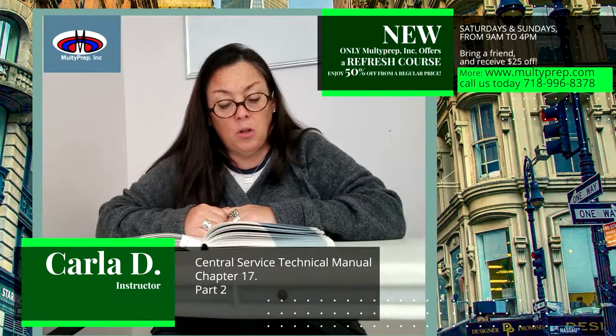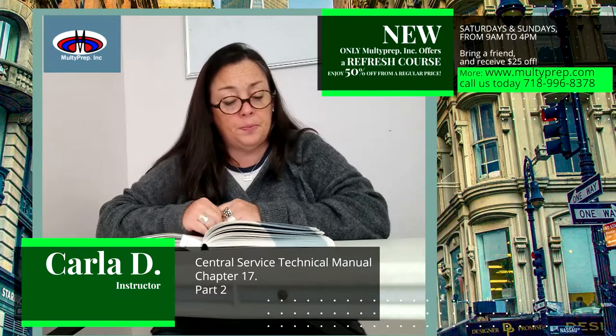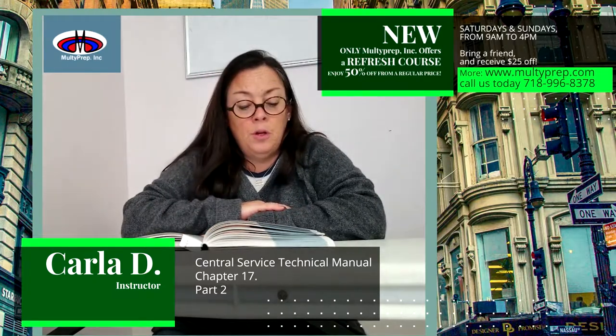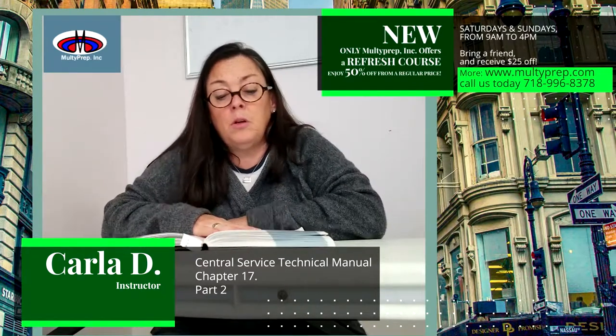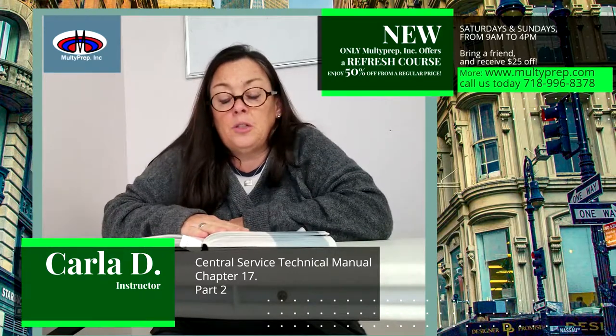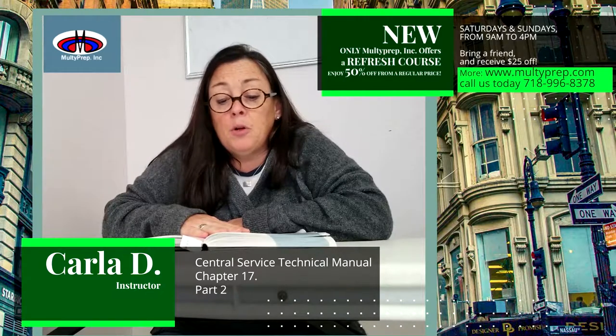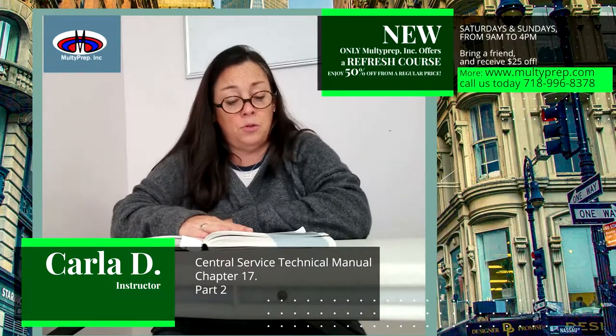It is assumed that killing all spores on a standardized BI indicates a successful sterilization cycle. This is because the biological indicator's population and resistance exceeds that of the bioburden on items being sterilized. Note, this assumption only applies to properly cleaned, prepared, packaged, and loaded supplies. It is recommended that a PCD be run in every ethylene oxide load. Note, it is essential that central service technicians are able to read and interpret physical monitoring information and chemical indicator color changes and know how to handle, use, and interpret the results of biological indicators.